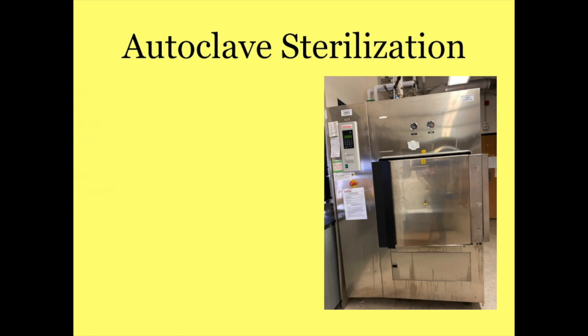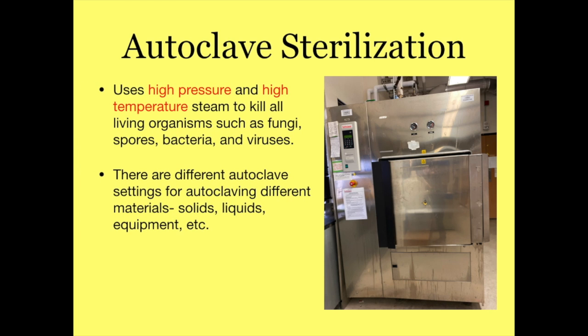Autoclave sterilization utilizes high pressure and high temperature steam to kill all living organisms such as fungi, spores, bacteria, and viruses. There are different autoclave settings for autoclaving different materials, such as solids, liquids, other equipment. The autoclave is like a giant pressure cooker since it utilizes steam sterilization.